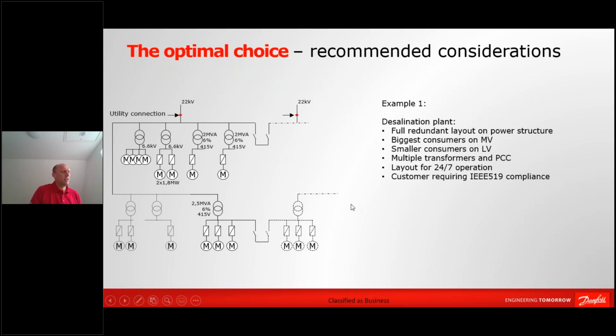The reason why this installation was done was to achieve full redundancy, and that means, for instance, that you can disconnect one of the supply lines, so one of the transformers can explode, and then you can supply the full desalination plant from the other. But that is only during emergency operation. So normally you would do two calculations here. You would do one for normal operation mode, and then you would do one for emergency operation mode. And then you will analyze the harmonics for both situations.